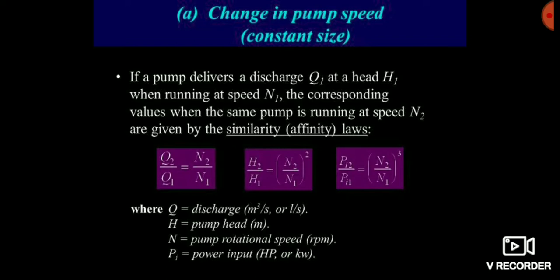So we simply put the speed value in place of discharge and get the answer. H2 by H1 equals (N2 by N1) whole squared, and N2 by N1 is directly proportional to Q2 by Q1. Therefore H2 by H1 is proportional to (Q2 by Q1) squared. Similarly, P2 by P1 is proportional to (Q2 by Q1) to the power 3.